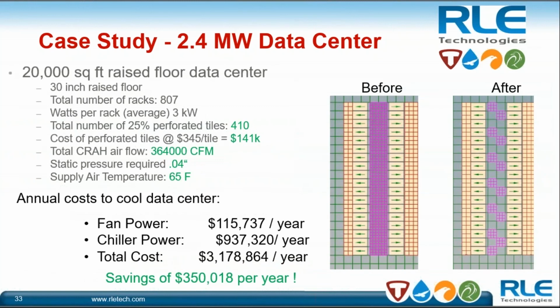So we came in and actually helped deliver a decreased number of performance panels required compared to the perforated tiles. Because of that, we were able to reduce overall CFM, but also able to increase the supply air temperature to 65 degrees versus 55, which made an impact of roughly $350,000 a year at this particular site.